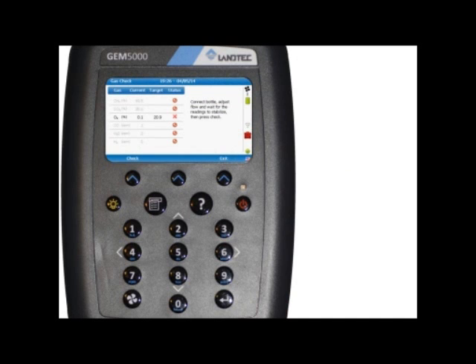After selecting the oxygen high gas mix, it will take you to the gas check screen, and by default the pump is configured to automatically turn on and pull ambient air. At this time, wait for the values to stabilize, and then using the left soft key, select check. Once again, this will activate the 1 minute timer. After the timer is complete, the complete message will appear showing the 3 options available to select. And once again, we're going to press the middle soft key to select calibrate.